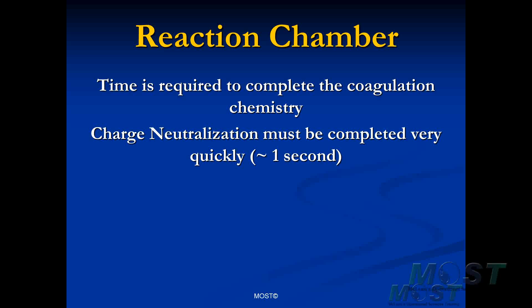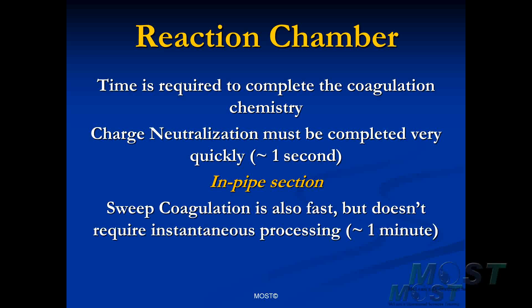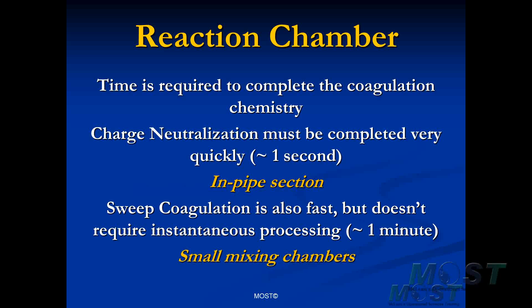With this small reaction time, all we really need in most cases is a section of pipe where we can accomplish charge neutralization. For the second form of coagulation, we also don't need very much volume in our reaction chamber because we only need about one minute to fully process coagulation. It doesn't require the instantaneous mixing that charge neutralization does, but this is also a fast process. So we will use a small basin for this, like a small mixing chamber.